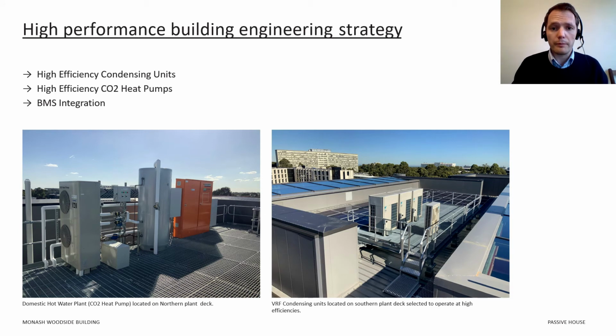The condensing units play a big role in energy consumption. Specifically for a large building like this one, where internal loads can be quite high, supplementary cooling and heating will be required. So, to meet the overall energy consumption benchmarks, the condensing units selected need to operate at high efficiencies. This is a fundamental step that can't be overemphasized. The same goes for the domestic hot water. If you want to meet the energy consumption benchmarks, then a stock standard air-cooled condenser won't do the trick. In this case, the domestic hot water system utilizes a CO2 heat pump, which offers significantly higher electrical efficiencies. We've also designed the system with well-insulated water storage tanks to assist with the fast response of hot water generation and reduce the need to constantly run the heat pump.